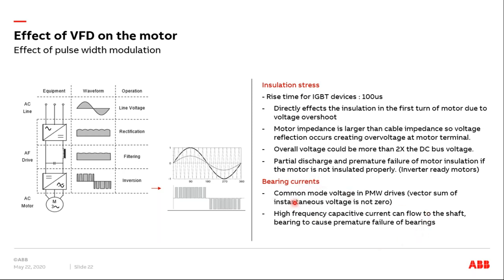Regarding the bearing current, it's the same thing. If you had a sinusoidal waveform, then at any instant of time, the instantaneous sum of all the voltages and currents is zero. But when you are using these square wave pulses, you have this common mode voltage, because this vector sum is not zero anymore.